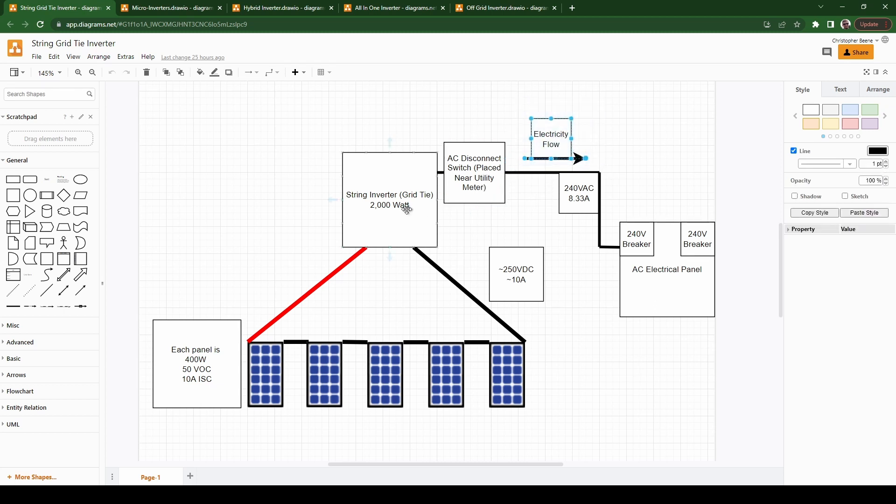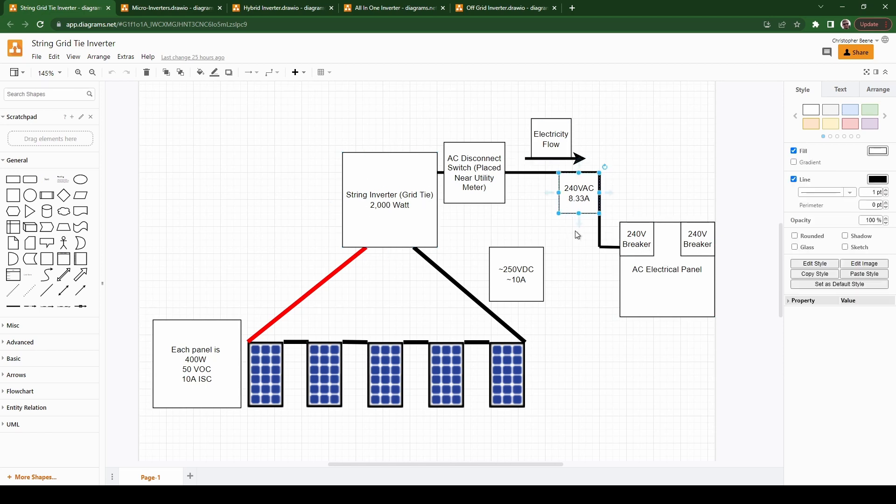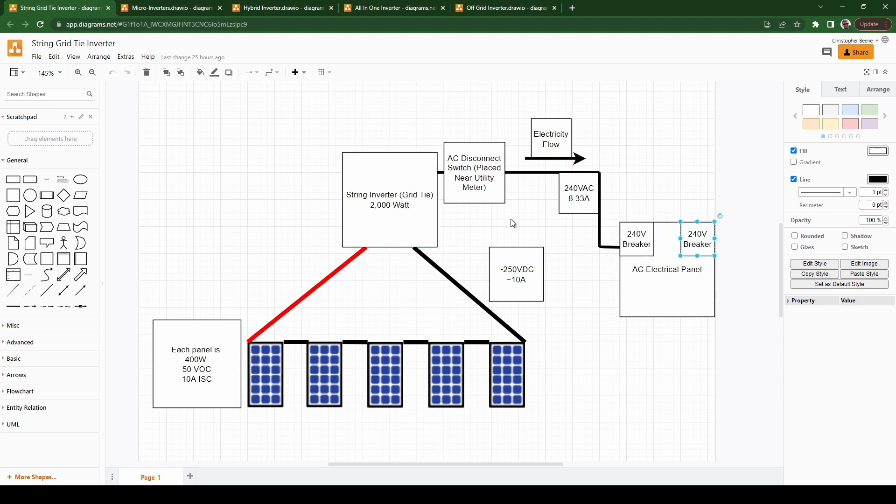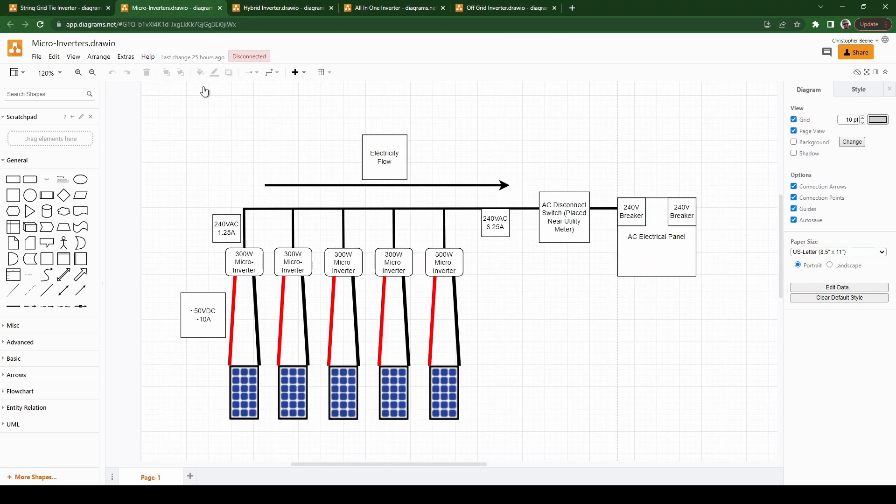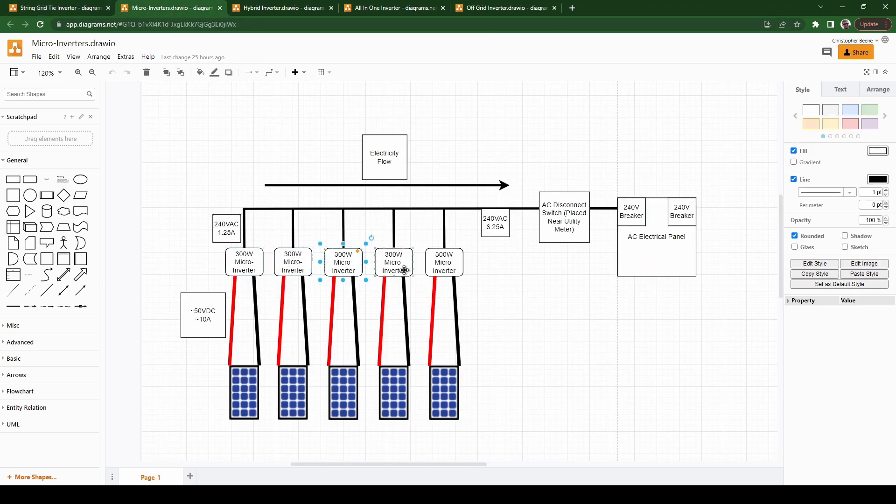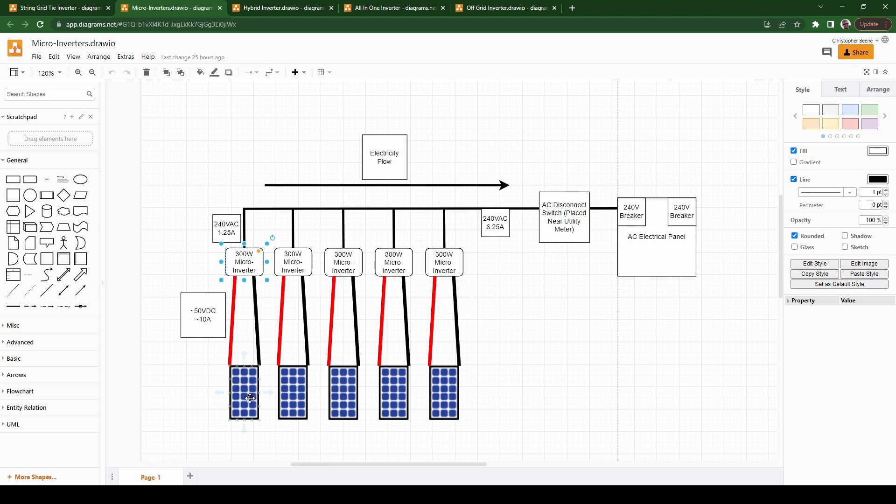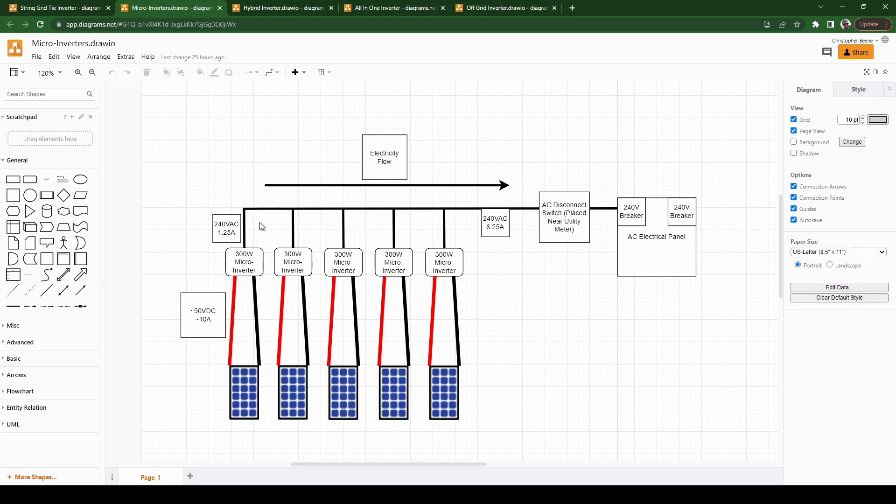The electricity is always flowing from the string inverter, from this grid tie string inverter into the electrical panel. So with a 2,000 watt inverter, I'm under 10 amps. You just feed it into a 240 volt breaker and everything's fine. If you ever wanted to add another string inverter you could just do another breaker. It doesn't have to be an upgraded inverter that's a larger wattage. You can actually run multiple inverters just like in micro inverters where you have multiple inverters and it's just that they're smaller inverters made to typically mount behind the panel itself.